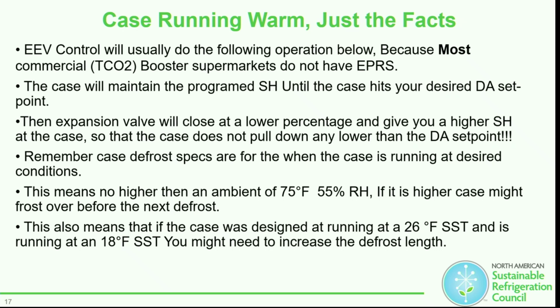Remember, the case defrost specs are only for when the case is running at the desired conditions. Dale's the one that told me that. Blame Dale. So if you have a case that's running, I'm sorry, I'll get there in a second, I just jumped. This means, remember the case defrost, running desired conditions, sorry. This also means that at a higher ambient than 75 degrees and 55% relative humidity, if it's higher than what that case spec is, then it could actually end up causing issues with frosting up, because there's more moisture within that case than what the manufacturer desired.